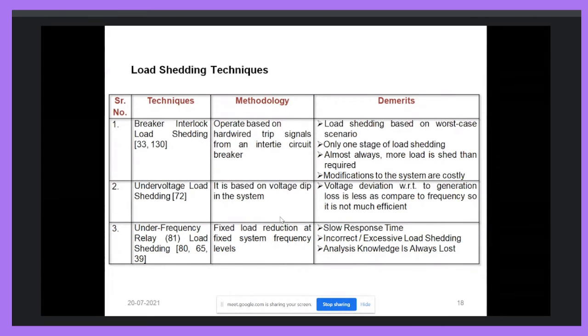Under voltage relay based load shedding is also there. It depends on the variation of the voltage. But the voltage deviation with respect to generation loss is less compared to the frequency. We all know that voltage is related to the reactive power balance of the system, and frequency is related to the active power balance of the system. So under voltage based load shedding is not very effective. Under frequency relay based load shedding has a problem of slow response. In addition, incorrect and excessive load shedding will always be there, because we designed this load shedding technique for the worst operating case. Worst operating means the maximum load and generation unbalance.